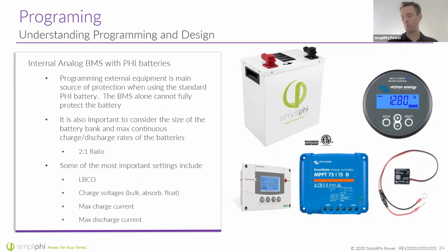Okay? If you discharge too fast, you produce too much heat inside the battery, and too much heat can damage the internals of the cells themselves. There's an organic electrolyte in there that can be vaporized if it's heated too high. So the C/2, or 2-to-1 ratio, means if we have a 4.98 or a 5 kilowatt hour battery, the output power of that battery would be 2.5 kilowatts. You can discharge a total of 5 kilowatt hours out of a battery. If it takes 2 hours to do that, you need 2.5 kilowatts for 2 hours.